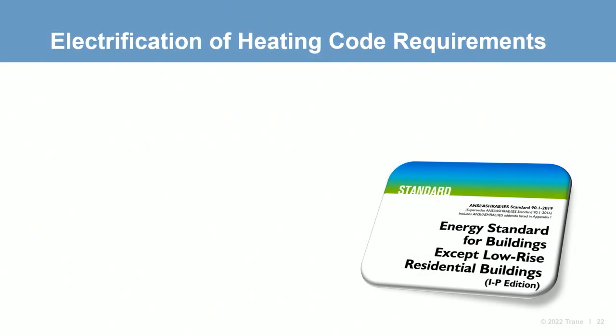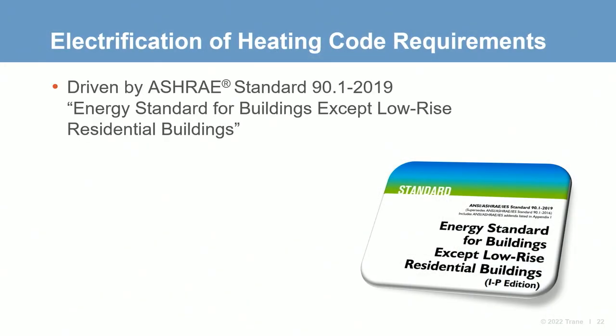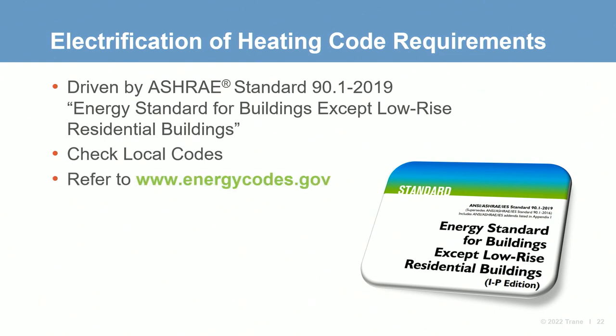For simplicity, and because it's adopted directly or by reference by most U.S. states, we'll concentrate on ASHRAE 90.1/2019 for code-related considerations and how they are applied to air-to-water heat pumps. Your particular jurisdiction may have adopted, modified, or eliminated these requirements. As always, we advise checking with your local code official or energycodes.gov to find out which requirements apply to your building.